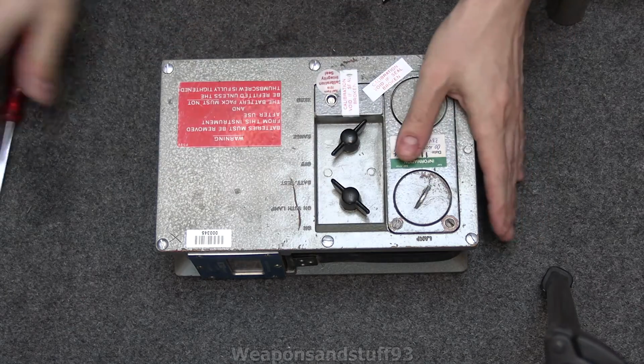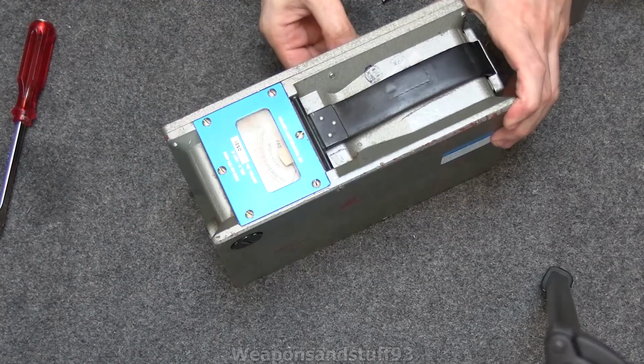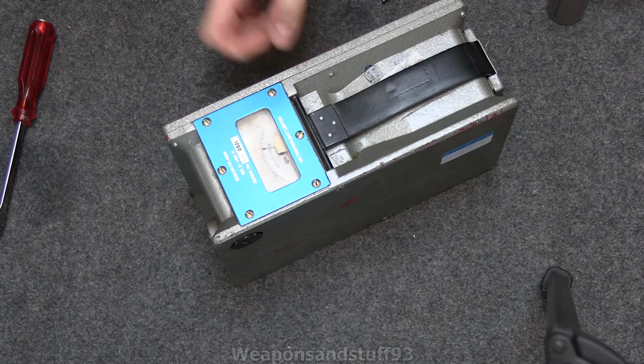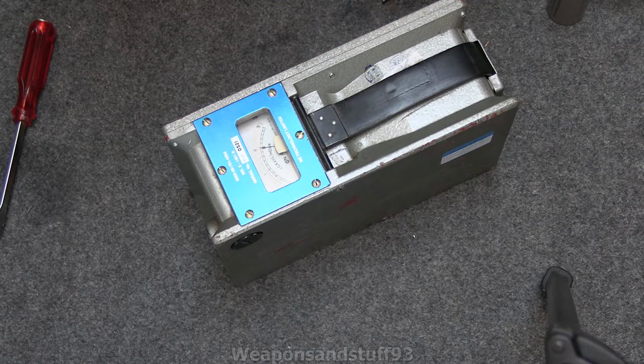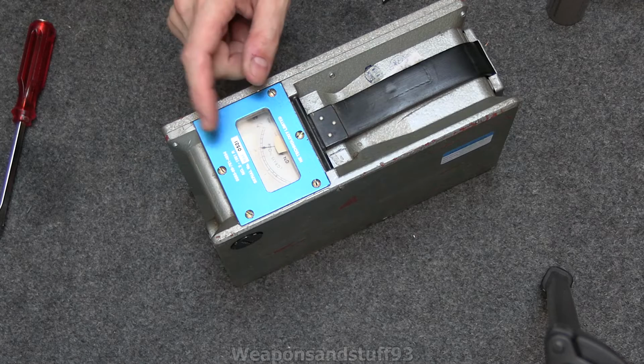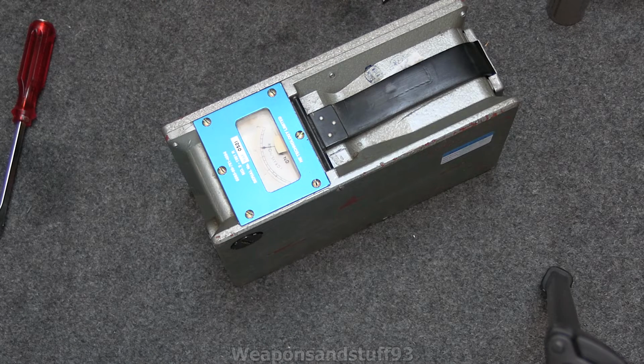So what we're going to do now is put the battery test on, see how that works. And it's above the top red line on the battery test, which is good. According to the sheet on how these work, if it's below the bottom red line, that means there's not enough energy in the battery to give accurate reporting. If it's between the bottom red line and the top red line, it means you've got about 20 hours left in the battery. If it's above the top red line like this one is, that's good. So the battery test works.